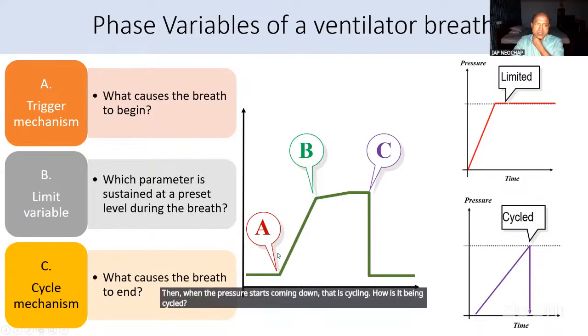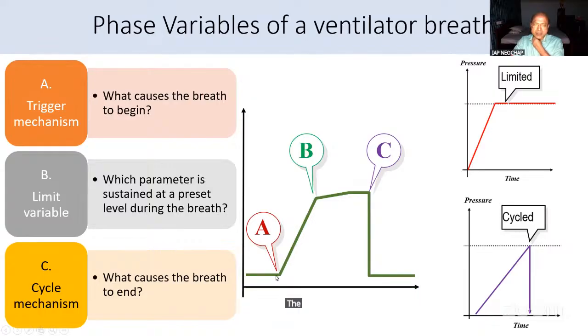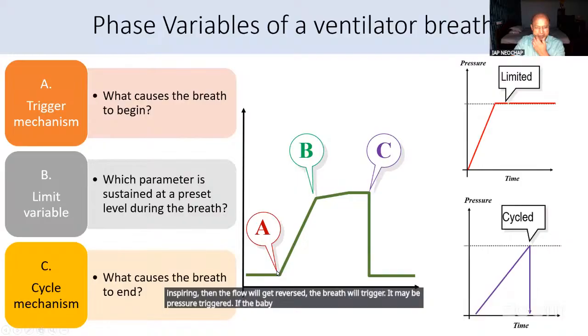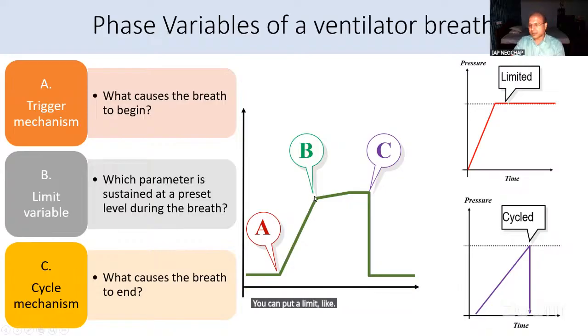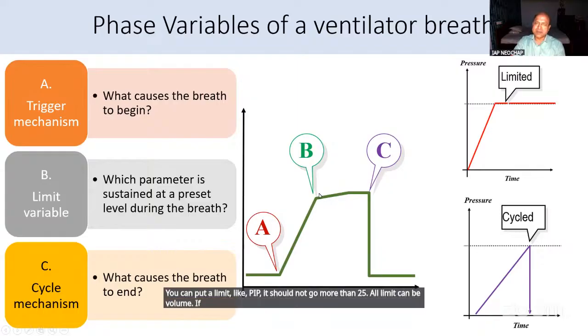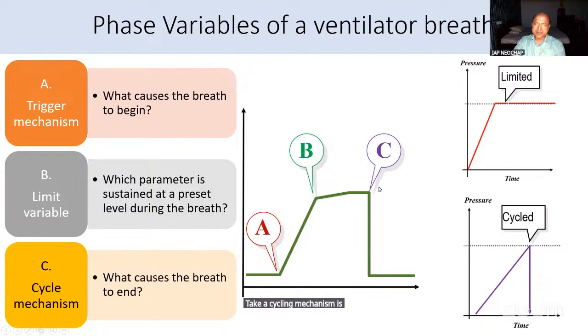So the trigger mechanism can be flow triggered. That means if the baby starts inspiring, then the flow will get reversed and the breath will trigger. It may be pressure triggered: if a baby starts breathing in, there is a drop in the circuit and the breath will trigger. Limit means you can put a limit like a PIP, it should not go more than 25. Or the limit can be volume: if 5 ml volume is delivered, it will stop ventilating the baby. Okay, cycling mechanism means when the breath will end.